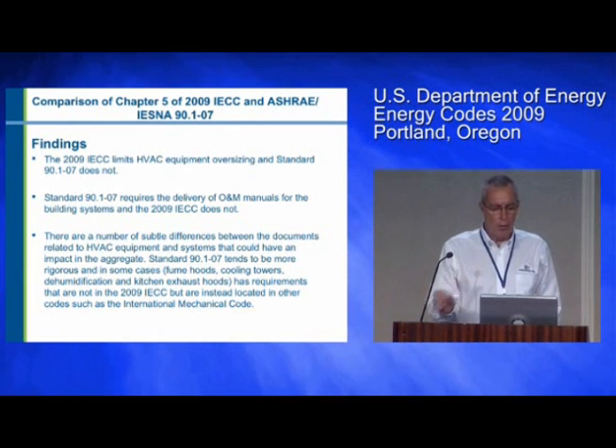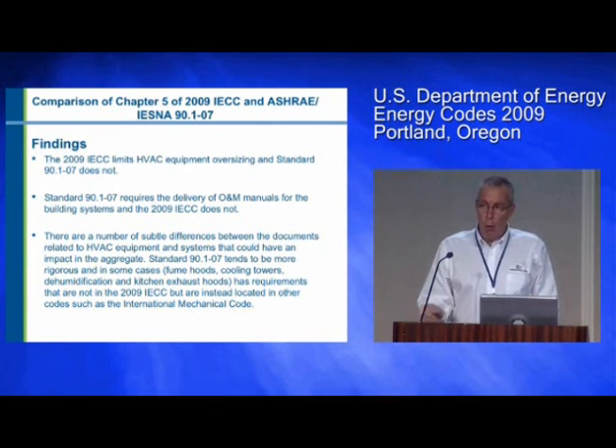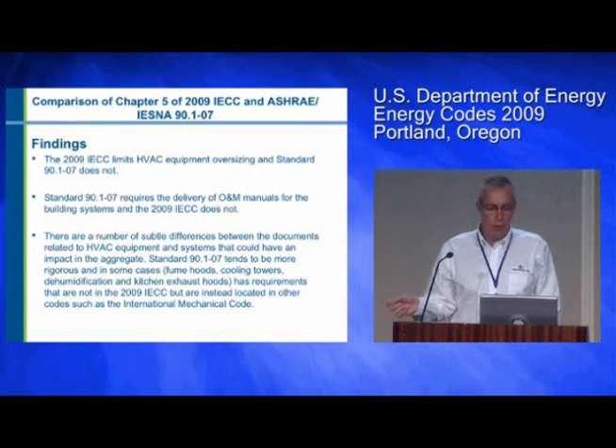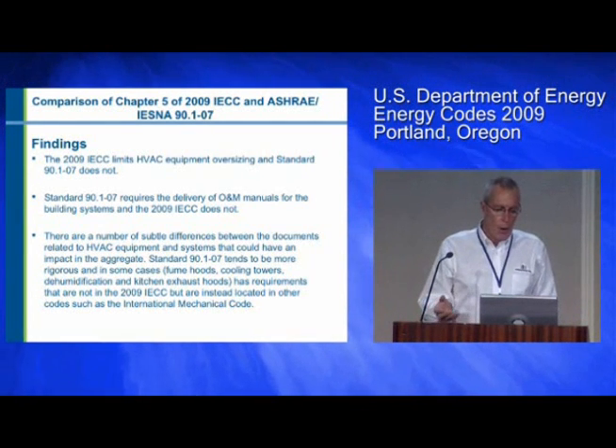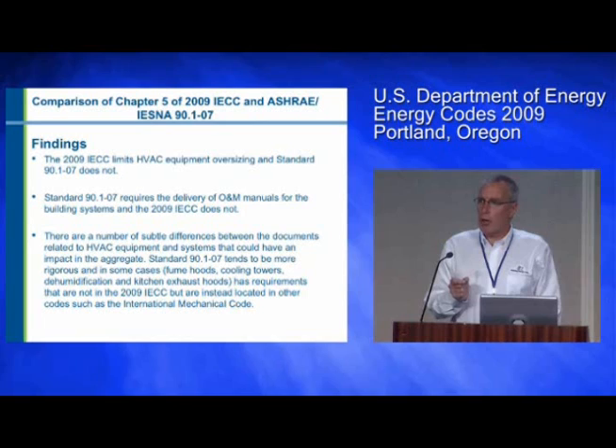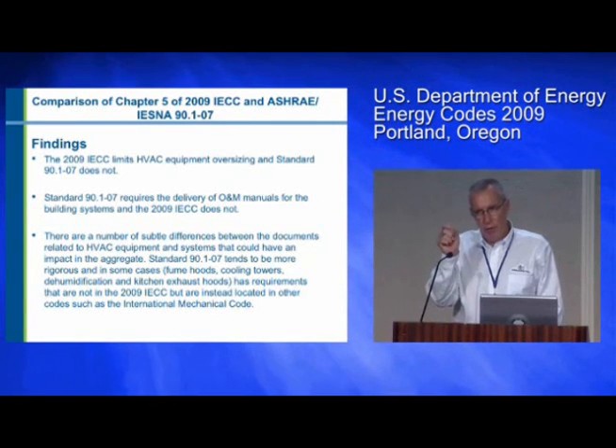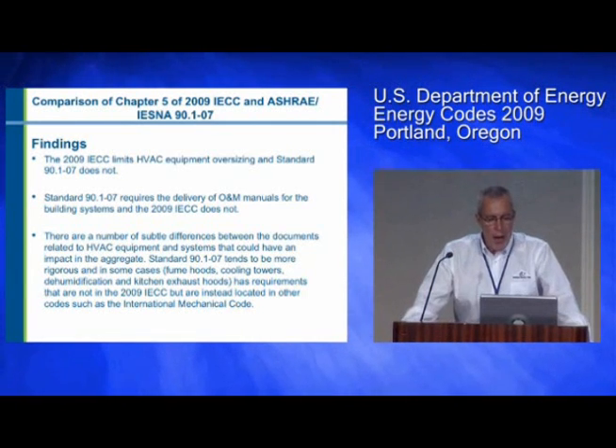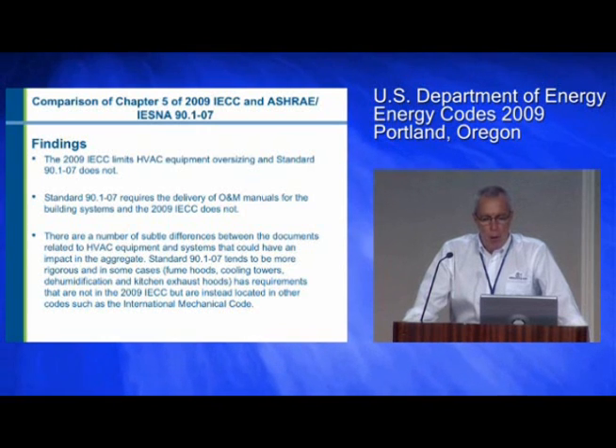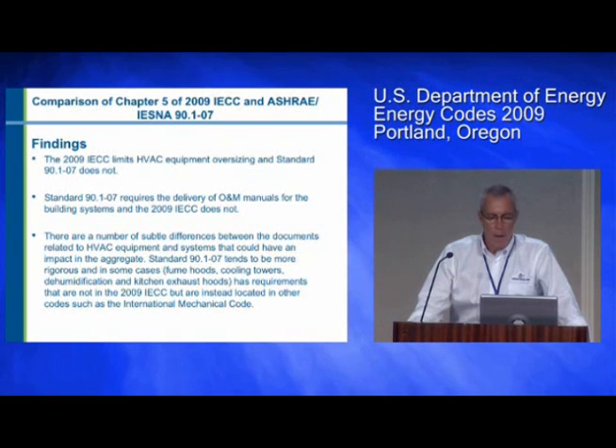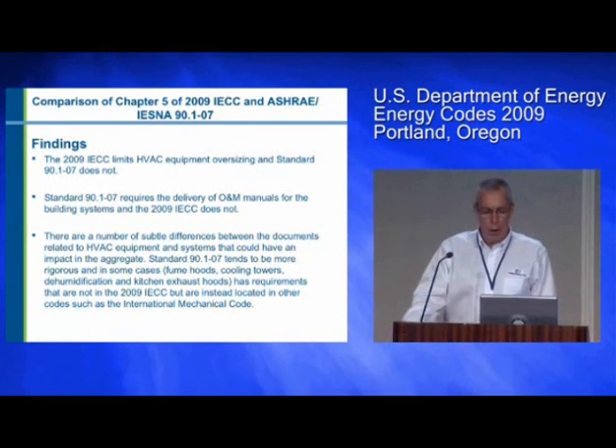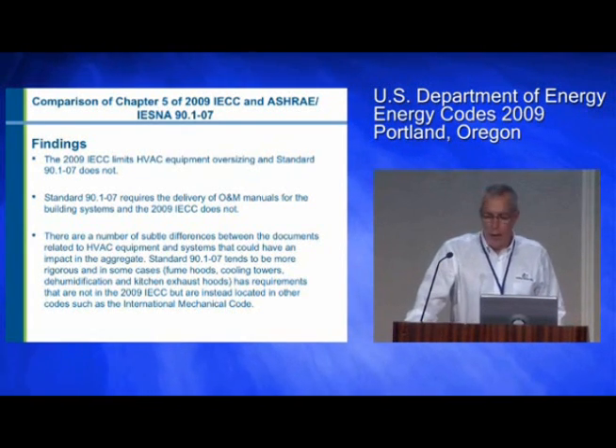I don't want to go into minute detail, but when you get into HVAC equipment, systems, controls, individually they don't look like much because it's kind of slightly different wording. But in the aggregate, 90.1 tends to be a little bit more rigorous in some cases. Fume hoods, cooling towers, dehumidification, kitchen exhaust systems where I'm doing energy recovery. And it has requirements that aren't in the IECC.